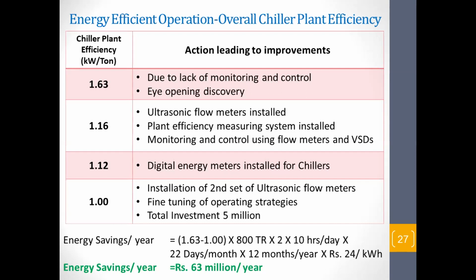and started monitoring or calculating the chiller performance online without a sophisticated energy accounting system. Just manual information extracted and calculated from time to time. And they have adjusted the chilled water and condenser flow rate as per the design requirements. With such a simple arrangement, they managed to bring 1.63 all the way down to 1.